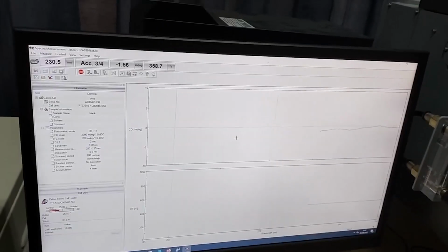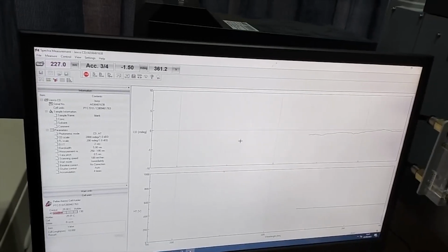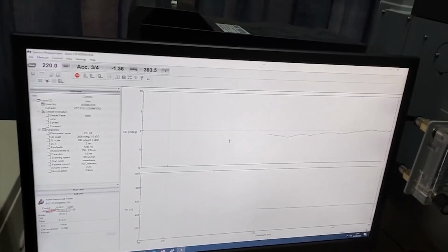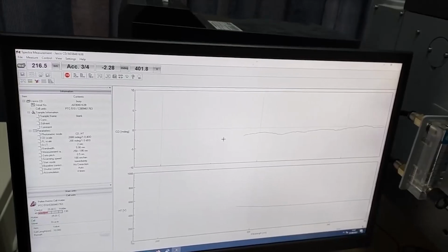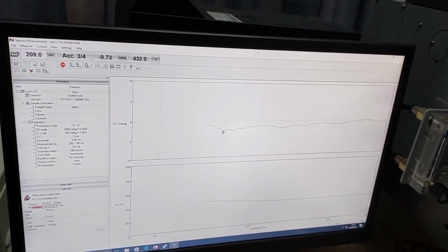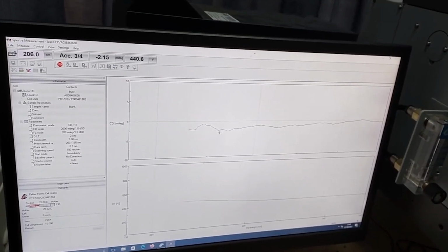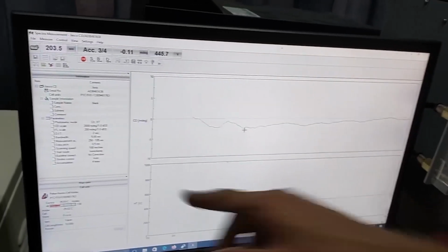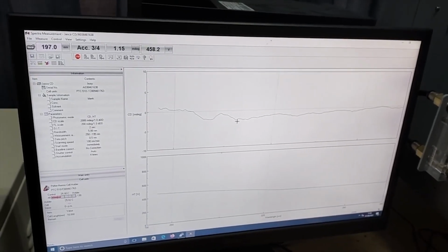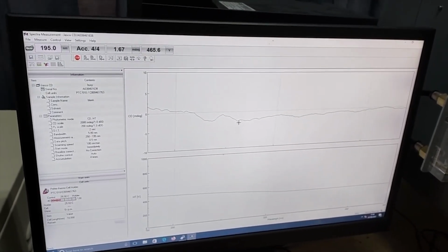the problem is. A very high voltage is applied when very few photons are reaching the detector. Under those conditions, your signal becomes noisy and unreliable. So one has to ensure that the CD voltage never exceeds 600 volts to get a reliable CD spectrum. It's no problem.